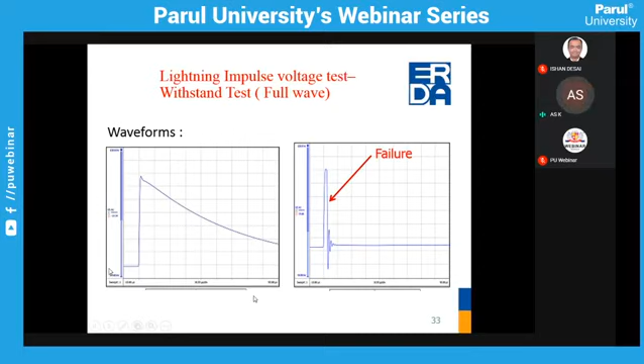Now, whenever we find out the flashover value, the standard has given two methods, that is multiple level test and up and down method. Multiple level means gradually we increase the voltage till we find out the flashover value. Up and down method means, let's say we gradually increase the voltage up to 100 kV and the product fails at 105 kV. Then again we'll have to reduce the voltage 5%, that is 100 kV, and we see whether the product is withstanding or not.